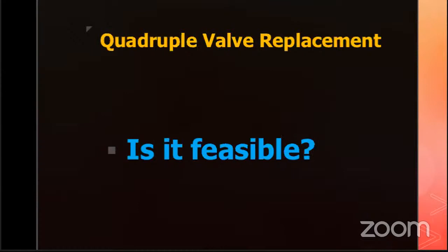The mechanical option at the present time that is available is probably only the bileaflet mechanical valve, with all of the companies using that same system. However, the companies differ in terms of the effective orifice area of the valve and the type of the sewing ring that the valve has. And because of that, and of course the hinge mechanism, you will see differences.